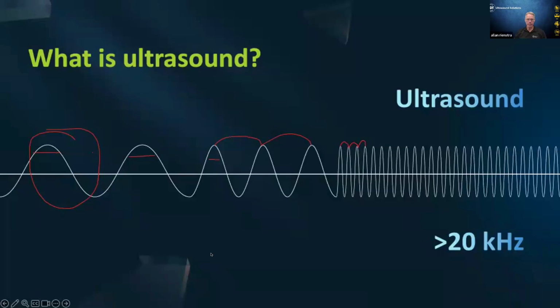What the shortening of that wavelength does is create three characteristics. One is distance. The higher we go in the frequency range, the shorter the distance that sound pressure waves can travel through their medium from source to sensor, whether that source be my mouth talking to your ears, or corona sizzling away on a high voltage transformer and being picked up by our sensor. The distance the signal can travel can be played to our advantage, because if we're trying to inspect a localized section of a substation, we just want to listen to the asset we're focusing on. We don't want to be interfered with by other assets and other sources of ultrasound nearby. So choosing 40 kilohertz as our listening frequency is advantageous in that sense.